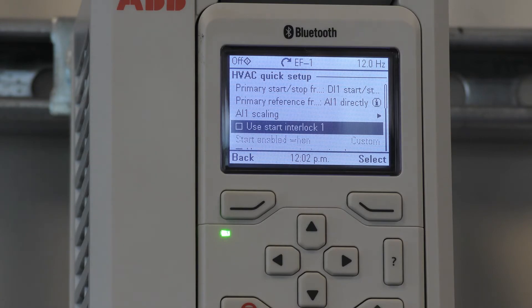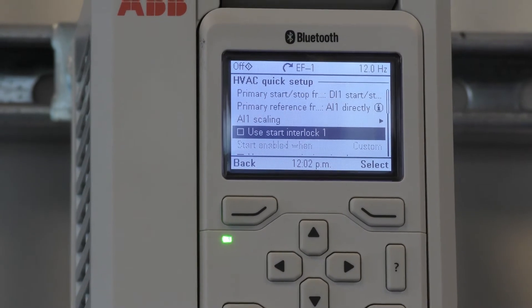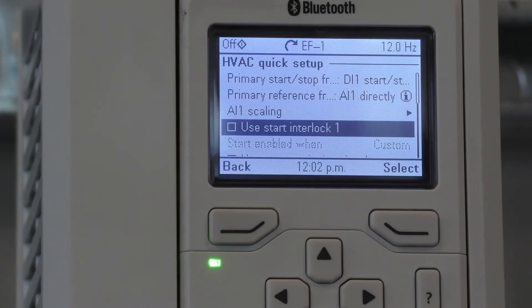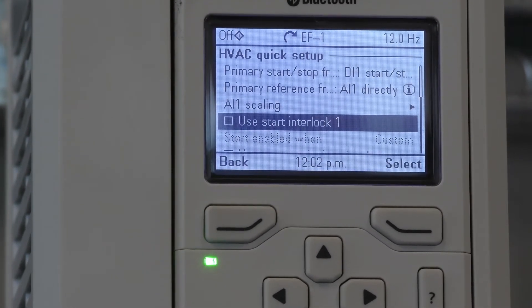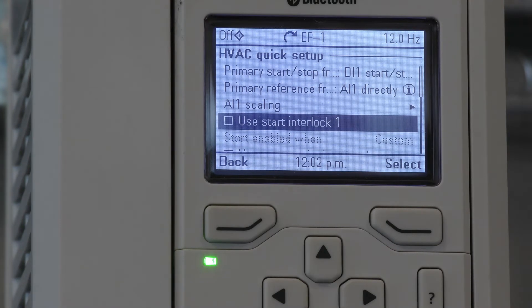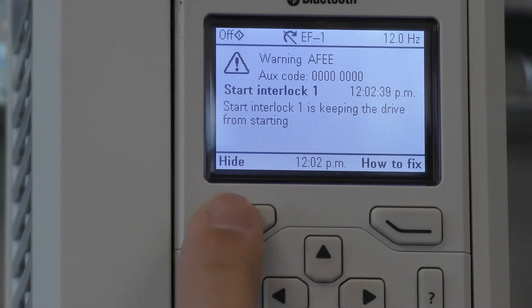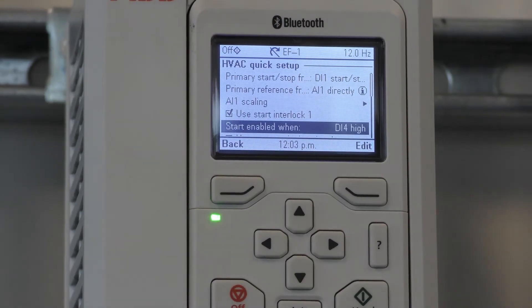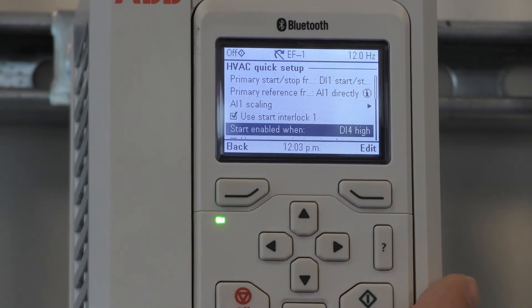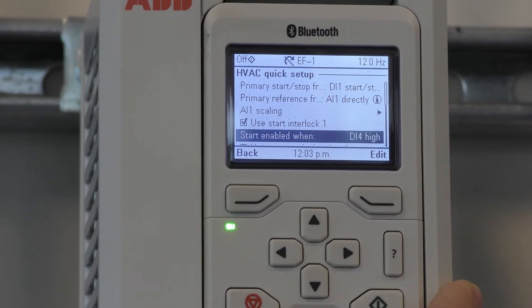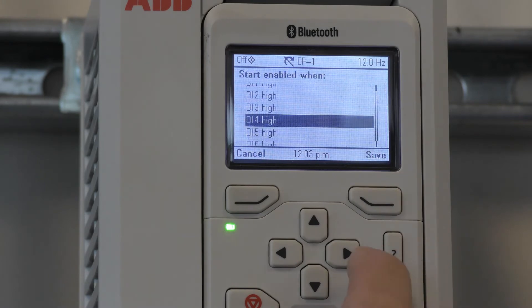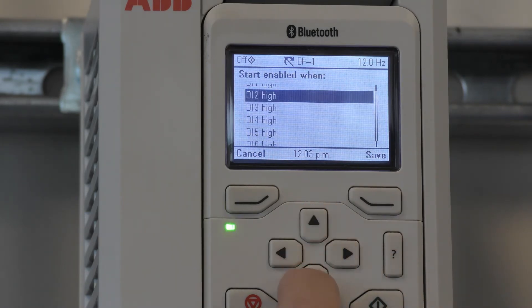This next parameter is where we would select the use of Start Interlock 1. This basically allows you to set up a digital input to utilize for safety purposes such as a freeze stat, fire alarm, or vibration switch. Here you can change whether you utilize DI4 high by pressing Edit, and you can choose one of the other digital inputs.